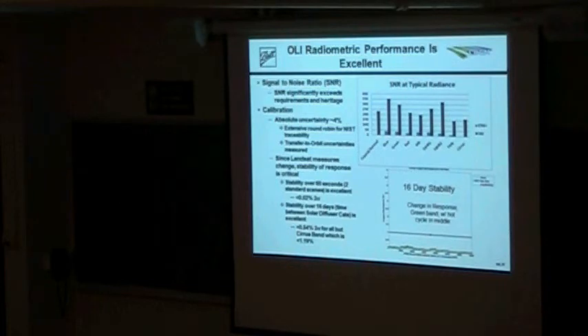The other thing that we had to demonstrate is that this thing was stable over time, stable between our calibrations. So we had to perform tests that showed the stability over 16 days, which is this chart right here. What you're looking at here is the green band over a 16-day period of time. You set up, you calibrate it. Then theoretically, if you calibrate it well, you take an immediate image and it hasn't changed. You get essentially a null signal against your calibration once you've applied your calibration coefficients. So the next opportunity on orbit we have to calibrate again is 16 days. So we had to demonstrate stability over that period of time, which we did in this thermal vacuum test. That's the stability of the green band in this particular chart versus our 1% requirement. So a very, very stable instrument.